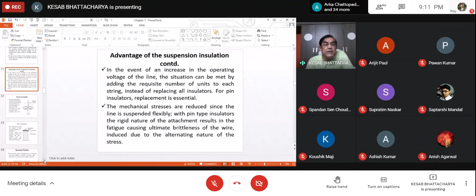Next, the mechanical stresses are reduced. When we use a single unit pin type insulator, the transmission conductors pass through the top groove and are tied tightly with the help of binding wire in the side groove, so mechanical stress develops. But in the case of suspension insulators, the transmission lines are suspended flexibly at the bottom of the suspension insulators, thereby reducing the mechanical stress developed. So these are the major advantages of suspension insulators.